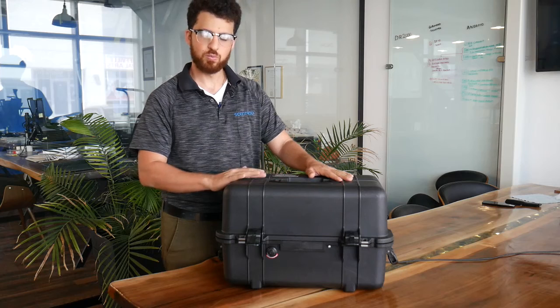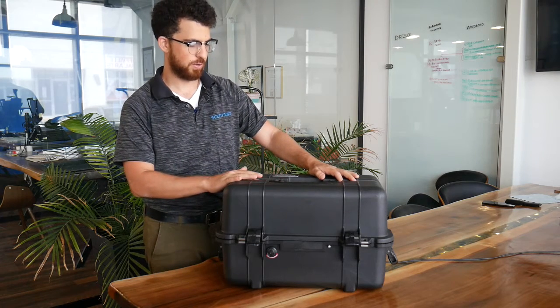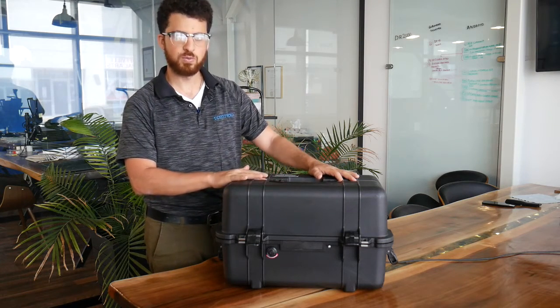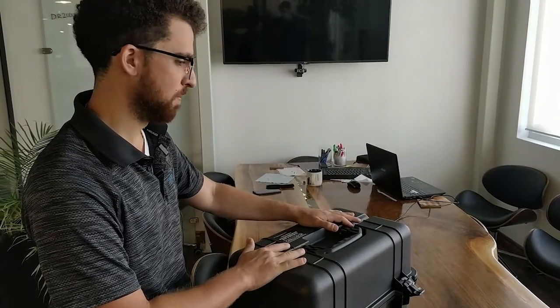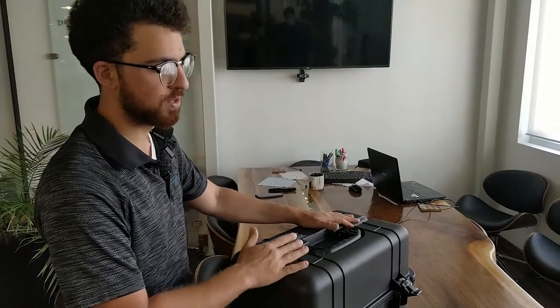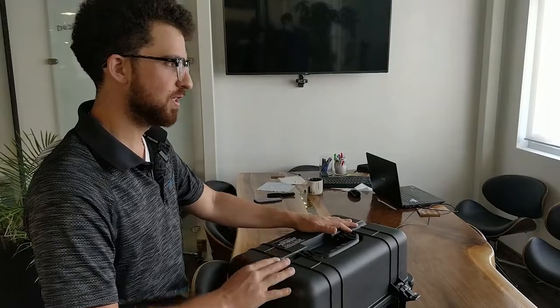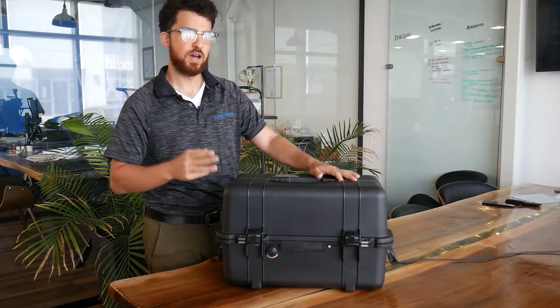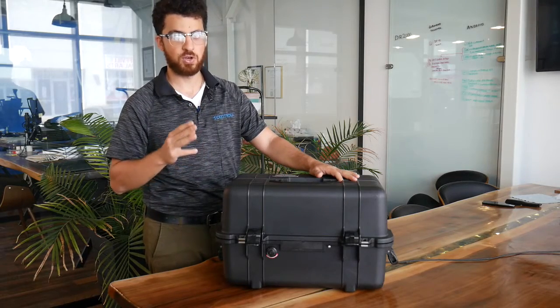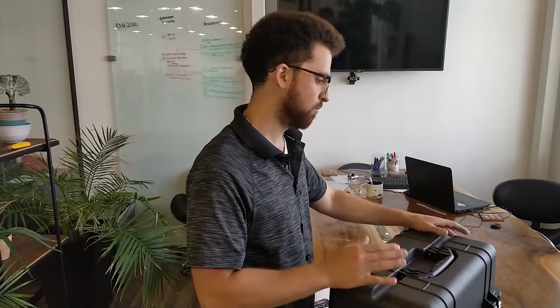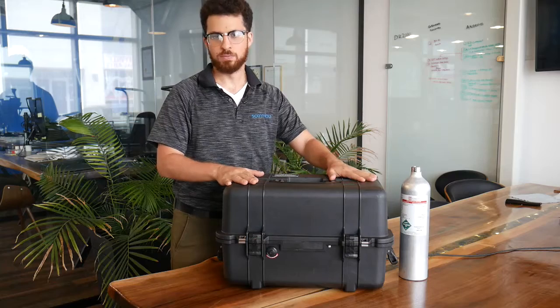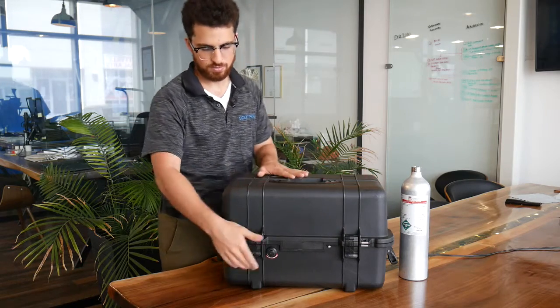The reason why we came up with this device is that on our products, we recommend a 3-point calibration. In order to do a 3-point calibration on our devices, you would need to get 3 different concentrations of your gas, which for sure is going to end up costing a lot. It's a perfect device to simplify calibration on any gas analyzer in the market. So let me show you the unit.